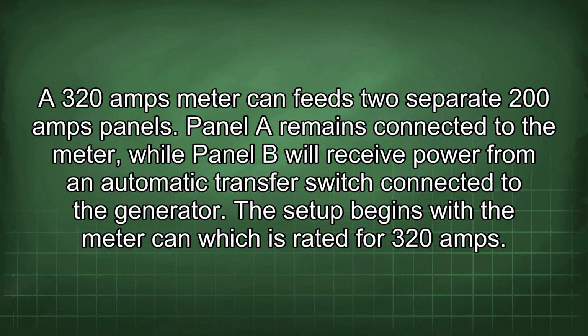A 320 amps meter can feed two separate 200 amps panels. Panel A remains connected to the meter, while panel B will receive power from an automatic transfer switch connected to the generator. The setup begins with the meter can, which is rated for 320 amps.